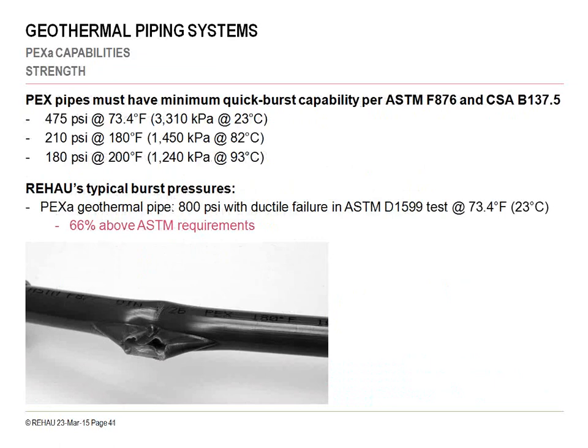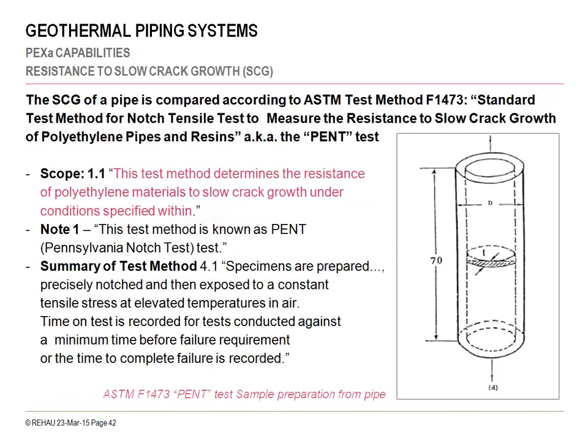These PEX pipes have minimum quick burst pressures, and you can see here, to the ASTM standard F876, 475 psi at 73.4 degrees Fahrenheit. RAUGEO actually internally tests the ductile failure to this ASTM D1599 at the 73.4 Fahrenheit temperature, and we are far exceeding the minimum of 475 psi, in the range of 800 psi to ductile failure.